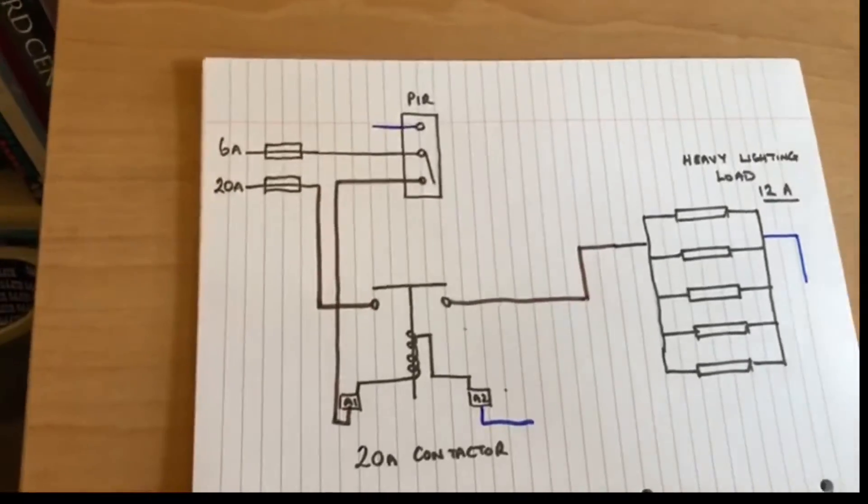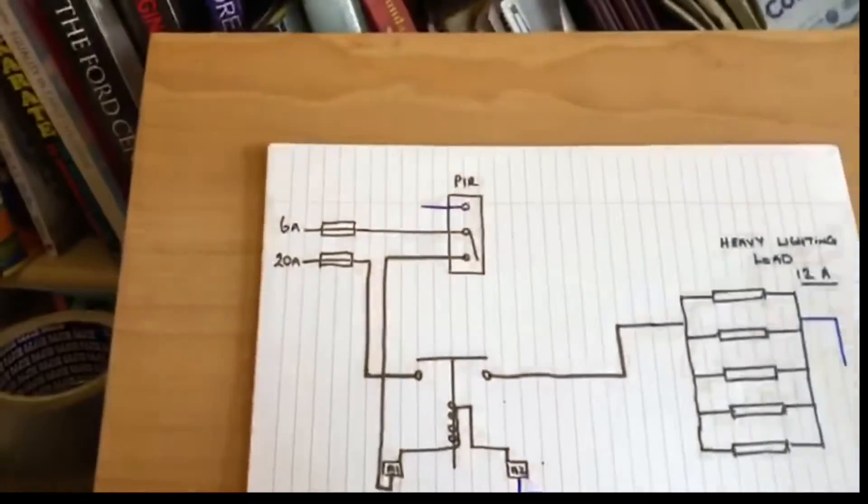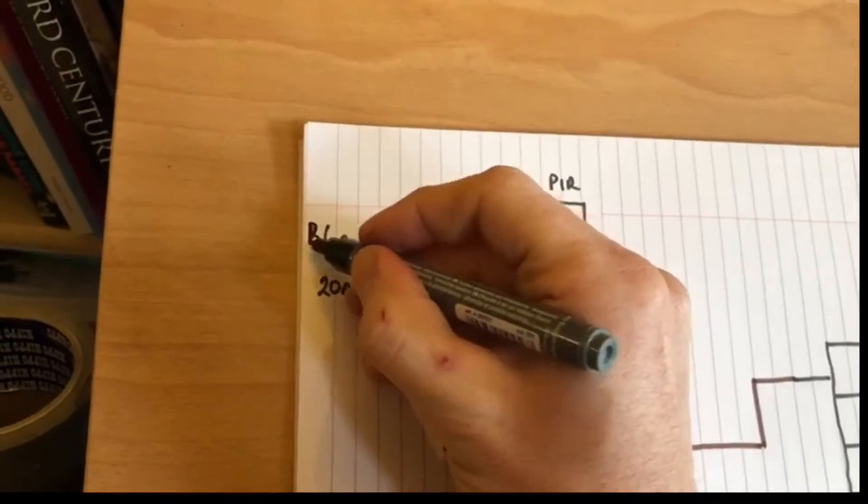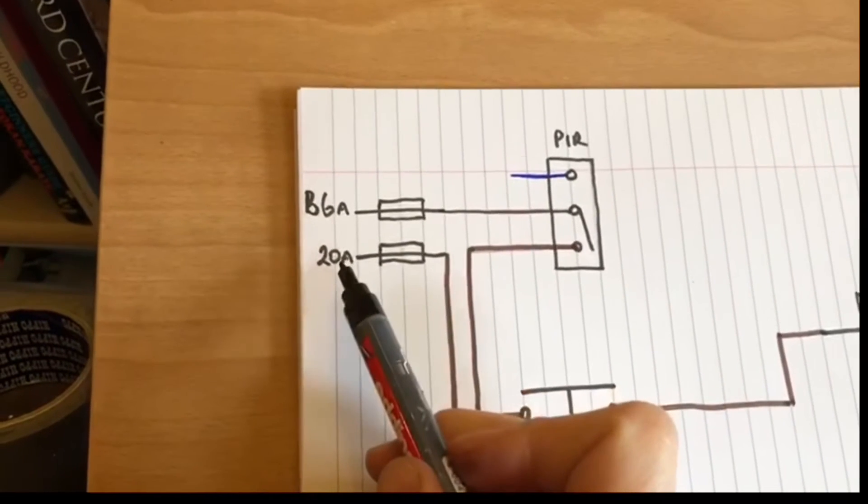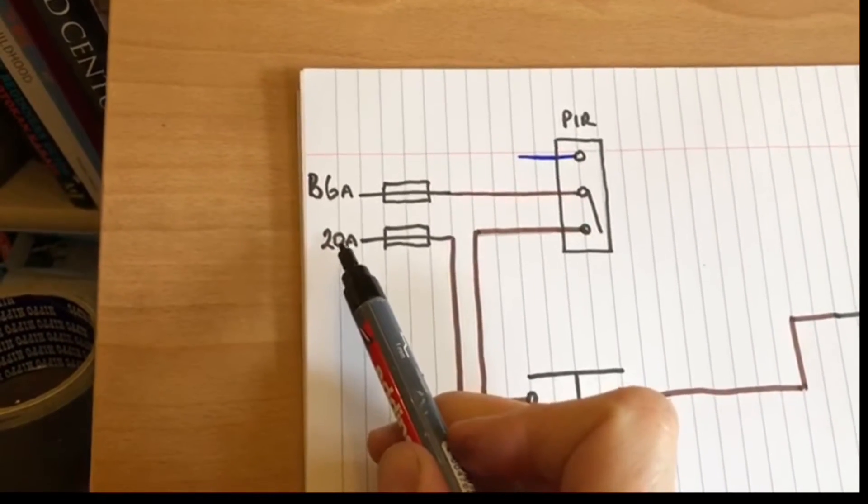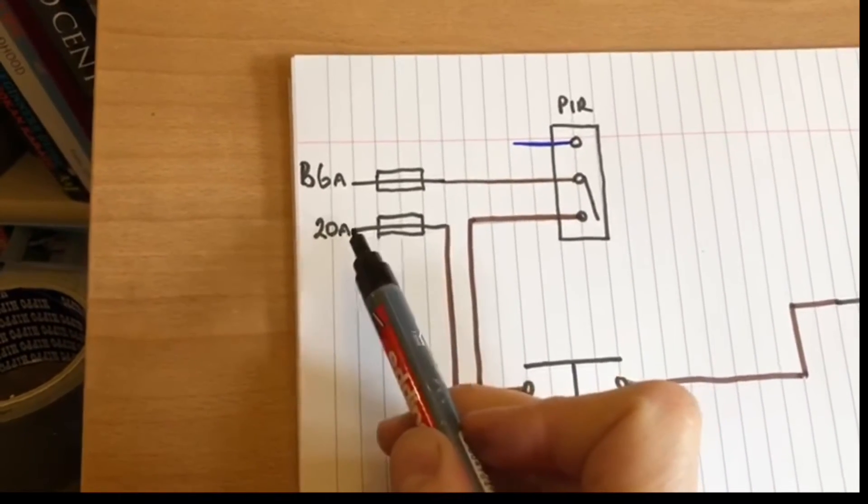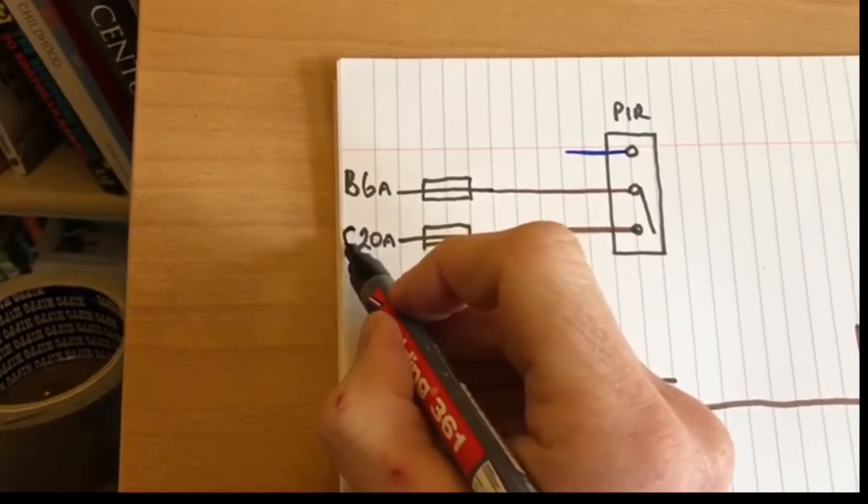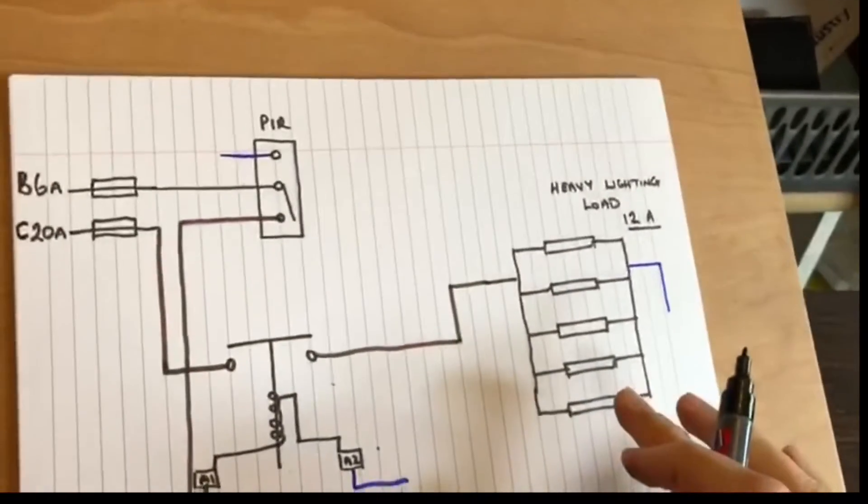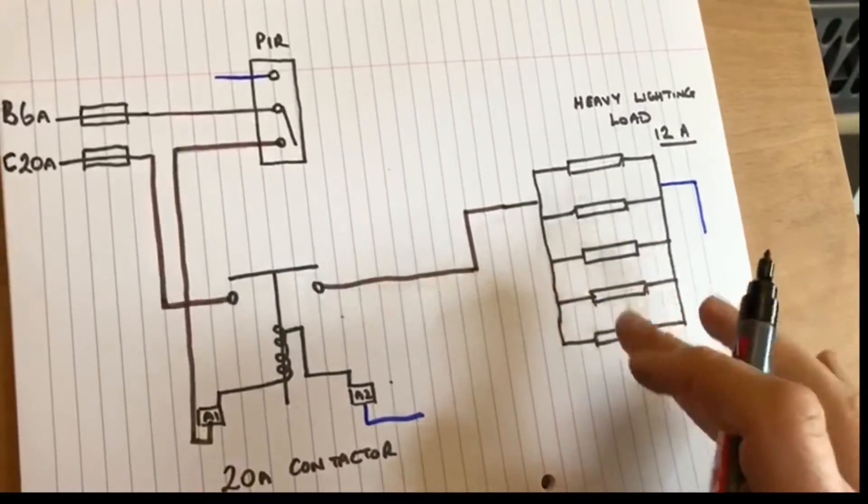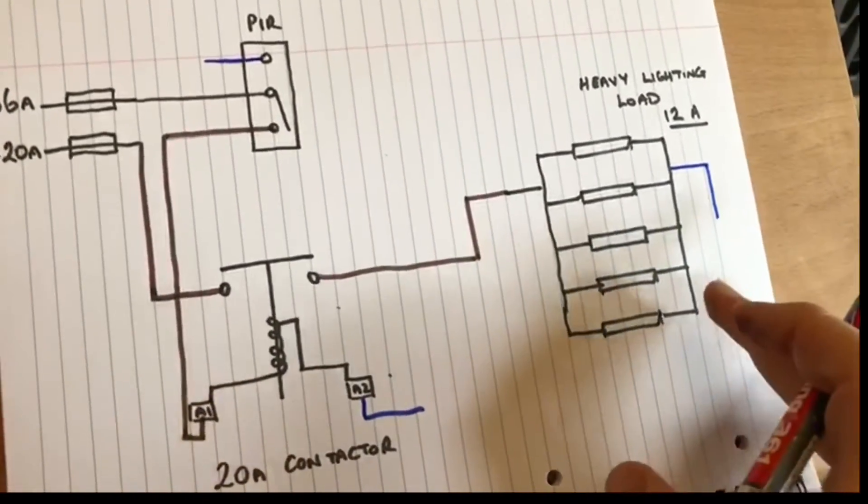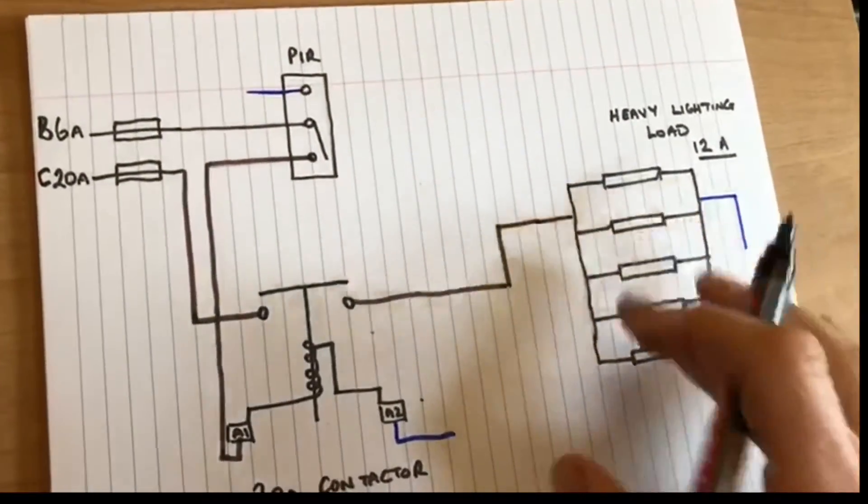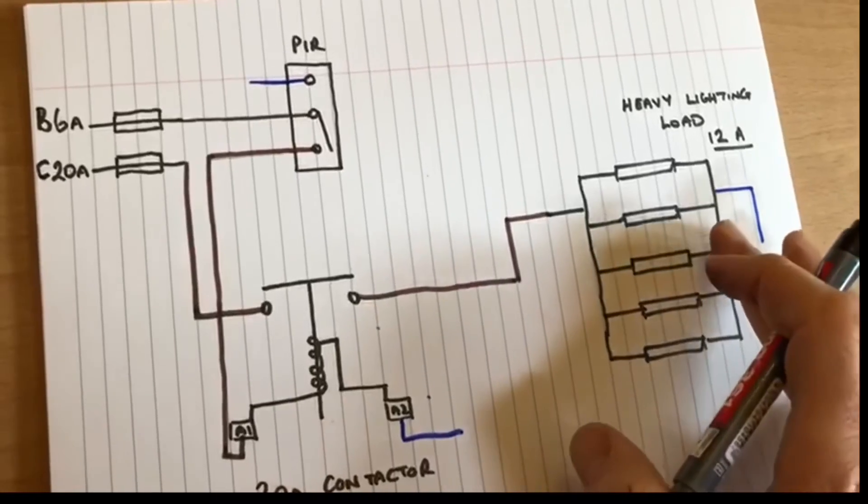Now let's just talk about the circuit breakers. The 6 amp circuit breaker only needs to be a B type circuit breaker. The other circuit breaker, and I've said a 20 amp circuit breaker but it might only be a 16 amp, that might be recommended to be a C type dependent on what the load is. Now if it's a fluorescent lighting load, it's probably important that it's a C type.